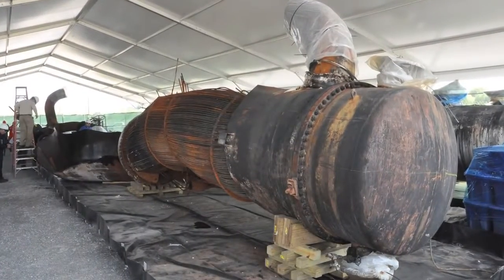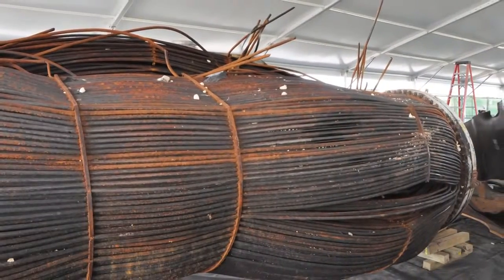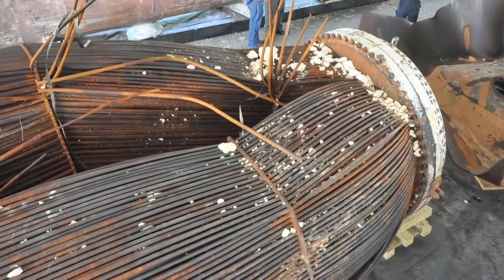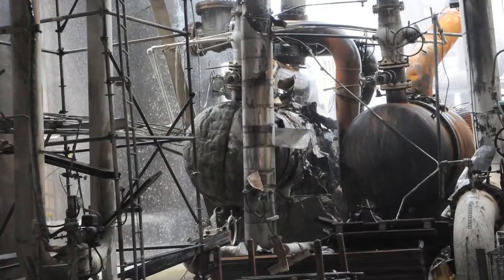During its investigation, The CSB found that prior to the explosion, the standby reboiler had been out of service for over a year, isolated from the process by closed block valves. But during this 16-month period, liquid propane unintentionally entered the shell of the reboiler, perhaps through a mistakenly opened valve or a leaking block valve.